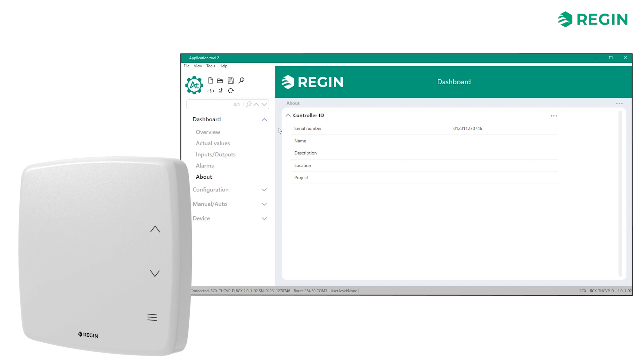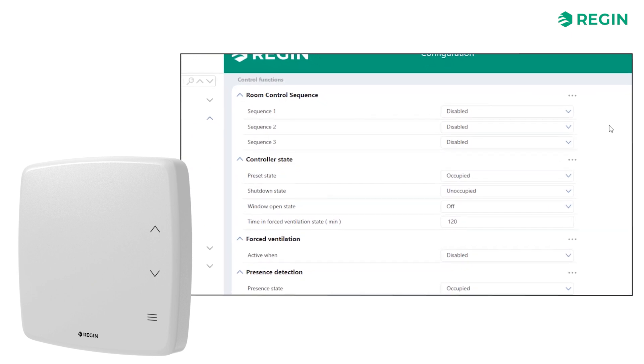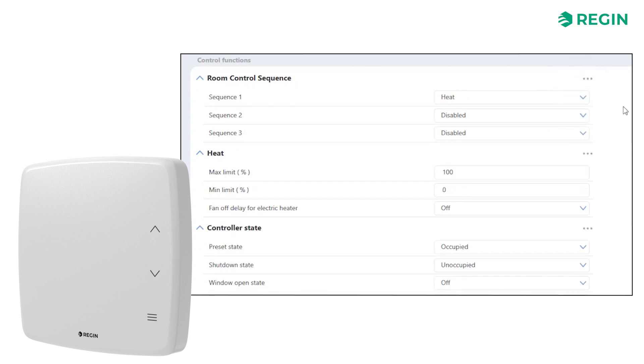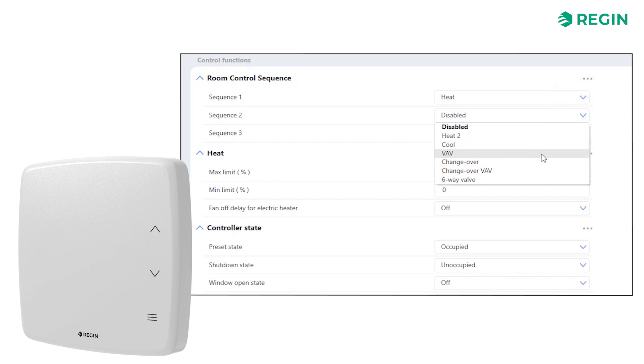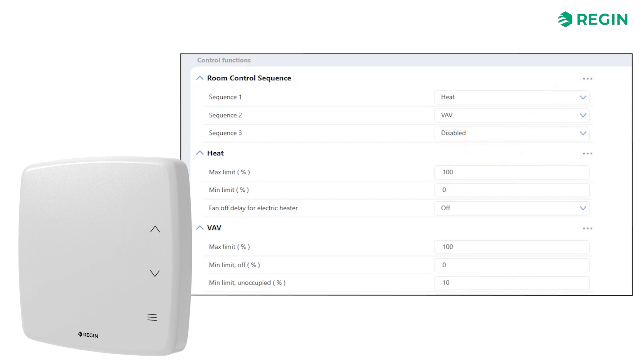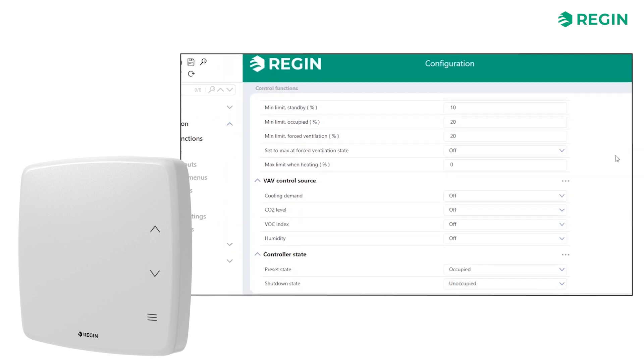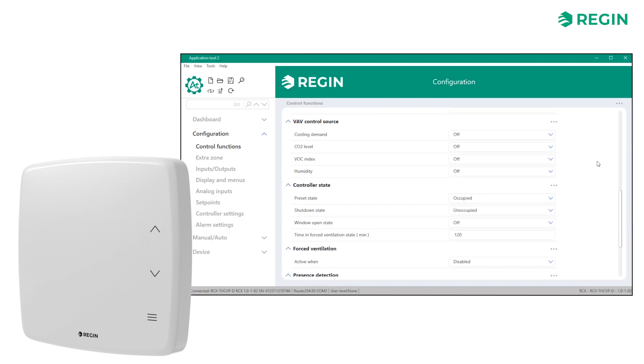When setting up the Regin RCX, your focus should be on the Configuration section. Let's start with the Control functions. For this example, let's set Sequence 1 to Heating, Sequence 2 to VAV, and Sequence 3 to Cooling. You can then choose to edit the maximum and minimum limits, but we will stick to the default values for this example. We can set the VAV control source to a selection of parameters — let's connect it to cooling demand, CO2 levels, and dehumidification.